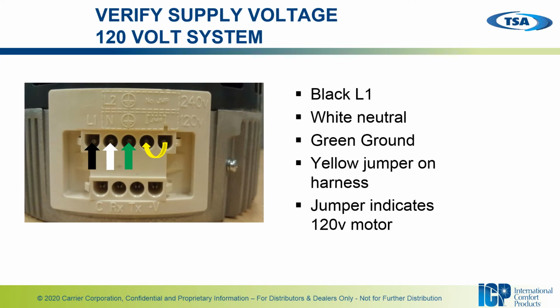Okay, so verifying high voltage to the motor, on your 5-pin high voltage connector, you're going to have a black wire going into your L1, a white wire going into your L2 or neutral, a green wire going into the ground, and then a yellow jumper harness. Okay, the jumper in the harness indicates that it's a 120 volt motor. Most people don't realize this, but ECM motors are typically dual voltage motors. And if the jumper's installed, it's 120 volts. If the jumper's removed, it's a 240 volt motor.